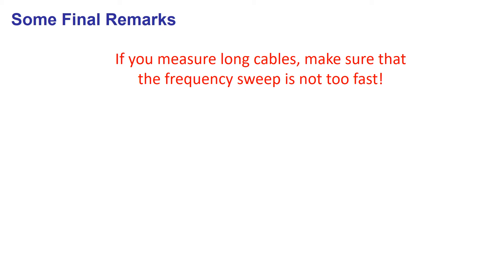...and this bandwidth is typically a few kilohertz, then the measured result will be in error by the roll-off of the IF filter. In this case, you might want to ensure that the sweep speed doesn't make any influence on your measurement.